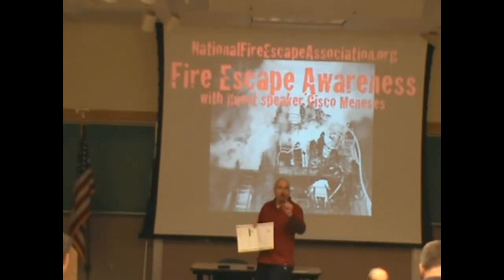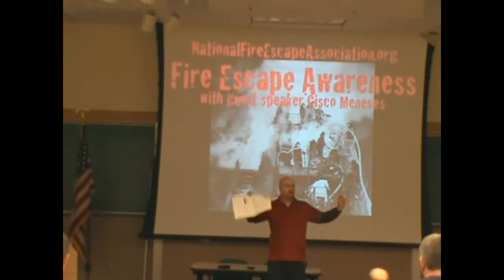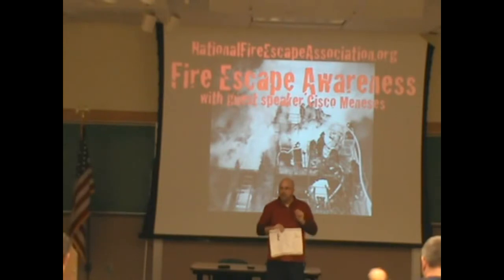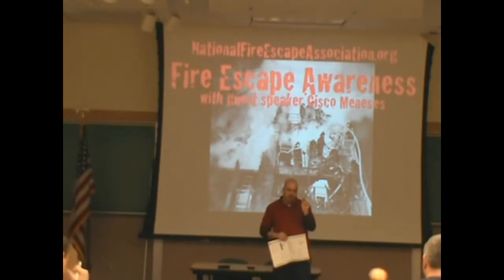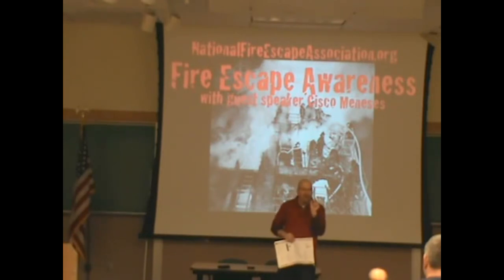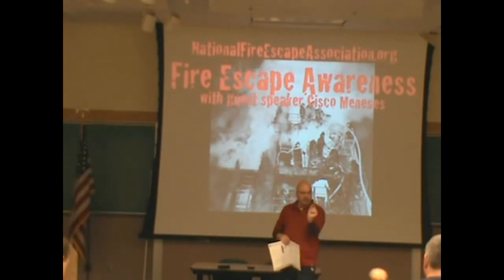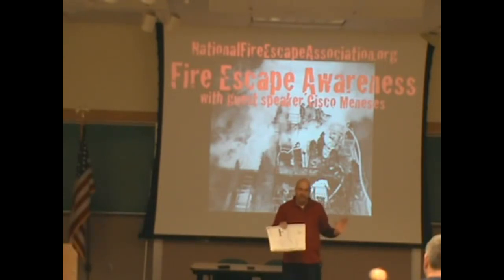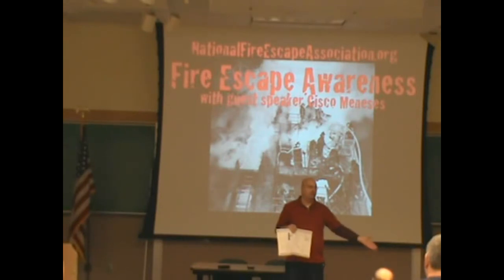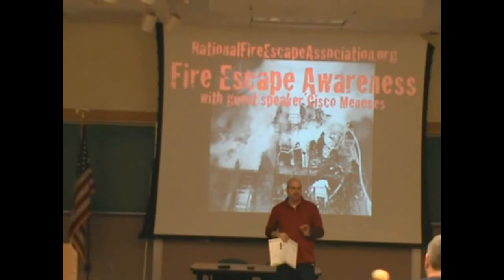We're going to prove today that all fire escapes rust from the inside out, not from the outside in. The first point of failure is at a connection — it takes 25 years to grow a quarter inch of rust, 50 years to grow a half inch. By the time you get to a fire escape with no paint left, how many years has it been rusting? At least 25. You can estimate how long the owner has ignored that fire escape. Can you load test a bad-looking fire escape? You can't — it's an automatic fail. You can only load test a fire escape that has passed a pre-load-test evaluation, which is a yes/no questionnaire.